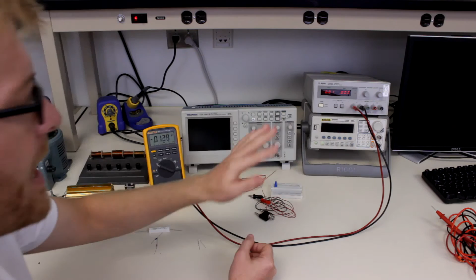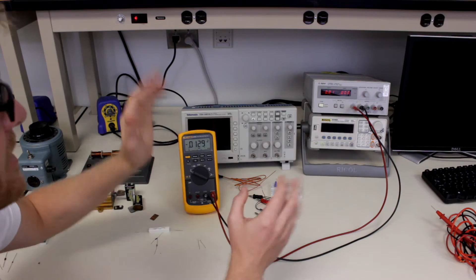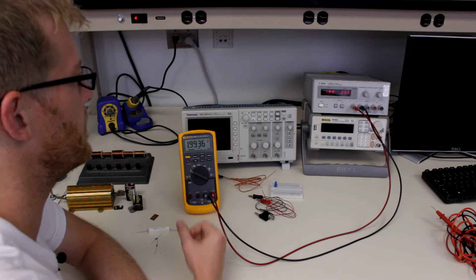Now the positive and negative terminals act like a variable battery, and we can see that this one goes from 0 to 25 volts DC, and as I increase the voltage, I see that I can measure voltage out to 100 microvolts, and the power supply indicates just down to 10 millivolts. So we get much better precision with this DMM.